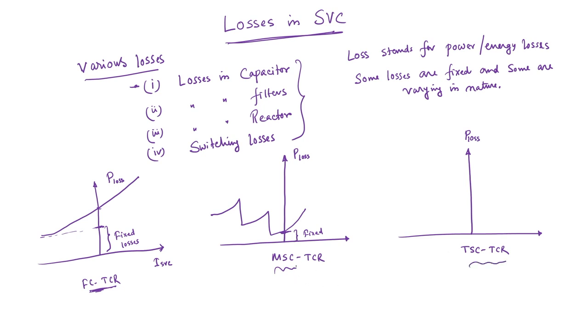Similarly for TSC-TCR, the characteristic is similar to MSC-TCR, but there are additional switching losses due to thyristor operation. So the fixed losses will be similar to MSC-TCR, and the overall characteristic will be somewhat similar as well, and so on. These are the comparative loss characteristics of the different types of SVC.